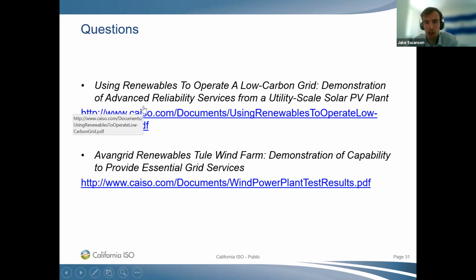What do you think is the minimum rotating inertia required by CAISO? We started looking at it, and I know GE looked at a study about two or three years ago. They looked at the West as a whole, and the ISO is part of the West, and they concluded back then that inertia was not an imminent problem for us. What was a problem was the frequency response capability of the system.